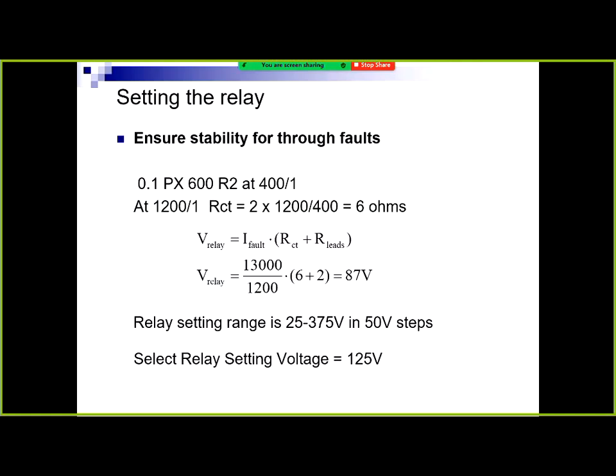So at 1200 to 1, the resistance of the CT is 6 ohms. That's our formula for the relay voltage: the fault current times the resistance. That's quite simple, V equals IR. We're talking in secondary terms, so we've got to convert the 13,000 amps to secondary amps. So that's why we divide it by 1200.